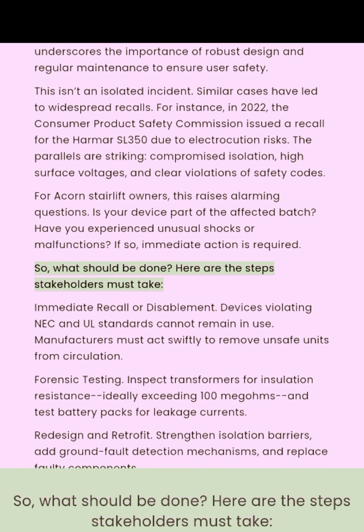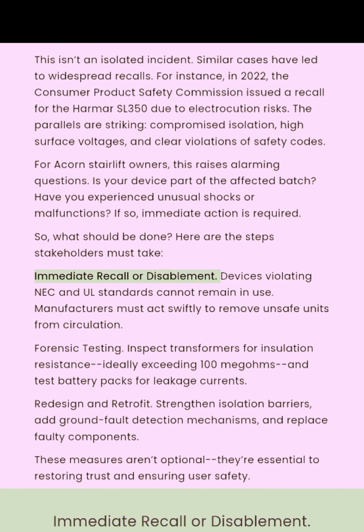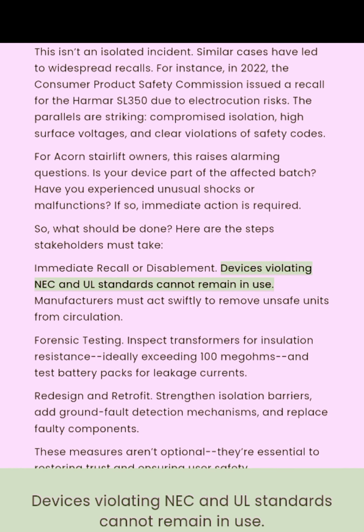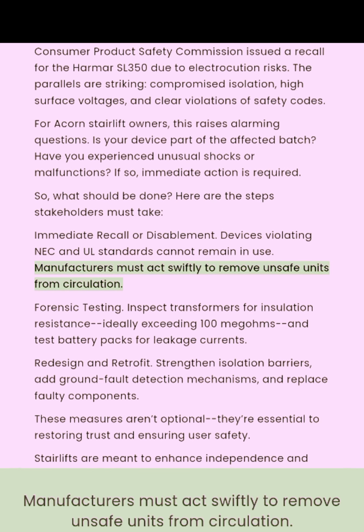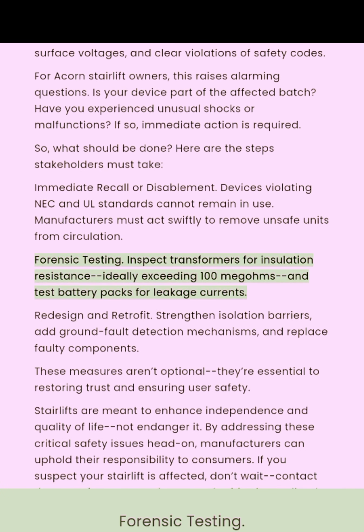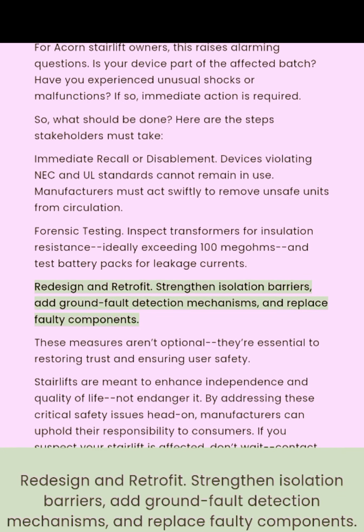So, what should be done? Here are the steps stakeholders must take. Immediate recall or disablement. Devices violating NEC and UL standards cannot remain in use. Manufacturers must act swiftly to remove unsafe units from circulation. Forensic testing. Inspect transformers for insulation resistance, ideally exceeding 100 megohms, and test battery packs for leakage currents. Redesign and retrofit. Strengthen isolation barriers, add ground fault detection mechanisms, and replace faulty components.